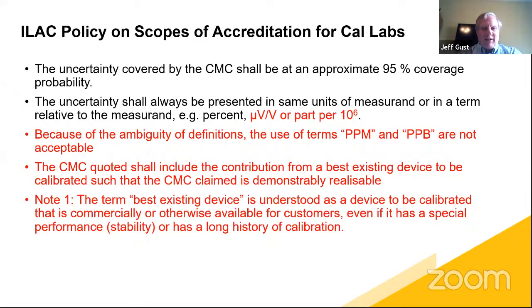The CMC quoted shall include the contribution of a best existing device to be calibrated, such that the CMC claimed is demonstrably realizable. So once again, we're closing the door. There were some loopholes about this before, but the point is your CMC should be realistic for the uncertainty for the device that you're going to calibrate, and the best device. So if you're calibrating DC volts and you've got a Keysight 3458, great, use that, that's probably one of the very best instruments. It gives you some of the smallest uncertainties realizable, or an 8588 from Fluke, same thing. But a device like that, if you have it.